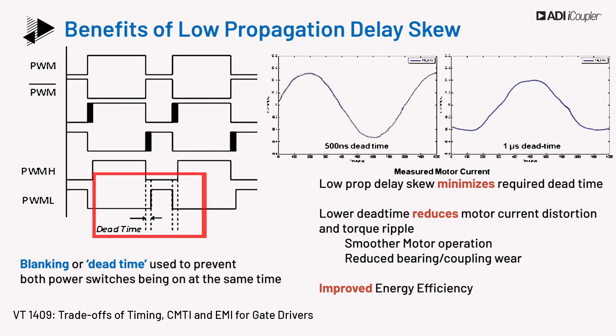A smaller skew allows a much tighter dead time to be set. Tighter dead time decreases motor current distortion and torque ripple, resulting in smoother motor operation and reduced bearing or coupling wear. Additionally, tighter dead time improves energy efficiency. Hence, for optimum efficiency, low skew is desirable.